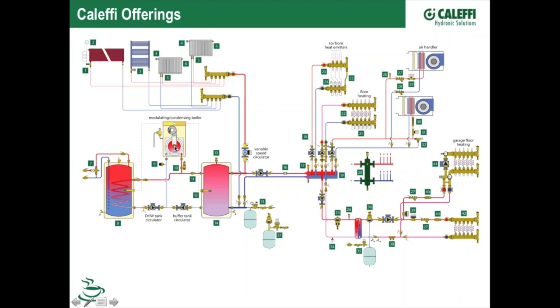What I see is a trend towards pressure switches in some of these boilers. So instead of using the flow switch, which we offer here, this is a paddle type of flow switch, and that's going to detect flow going through it. And if there's no flow, it interrupts the signal to the pump or to the boiler, to all the equipment in here, and it shuts it off. Another way of doing that is to have a pressure switch, which you'll see in a lot of these boilers, right up here on the boiler, and that's going to tell you that if the pressure drops in the system, it's going to drop the burner off.